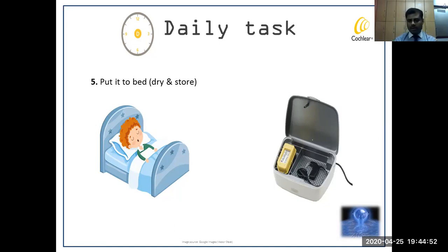What's more important is when you use the dry aid store, you have to put the entire processor inside. Some people have a habit of just putting the processor and not the battery component or the coil, so we advise putting the entire processor inside and storing it overnight. If you're using an electronic dry aid kit, make sure it's working - some are battery operated, some require AC current directly. Make sure you plug it in and it gets power supply, otherwise it won't work.